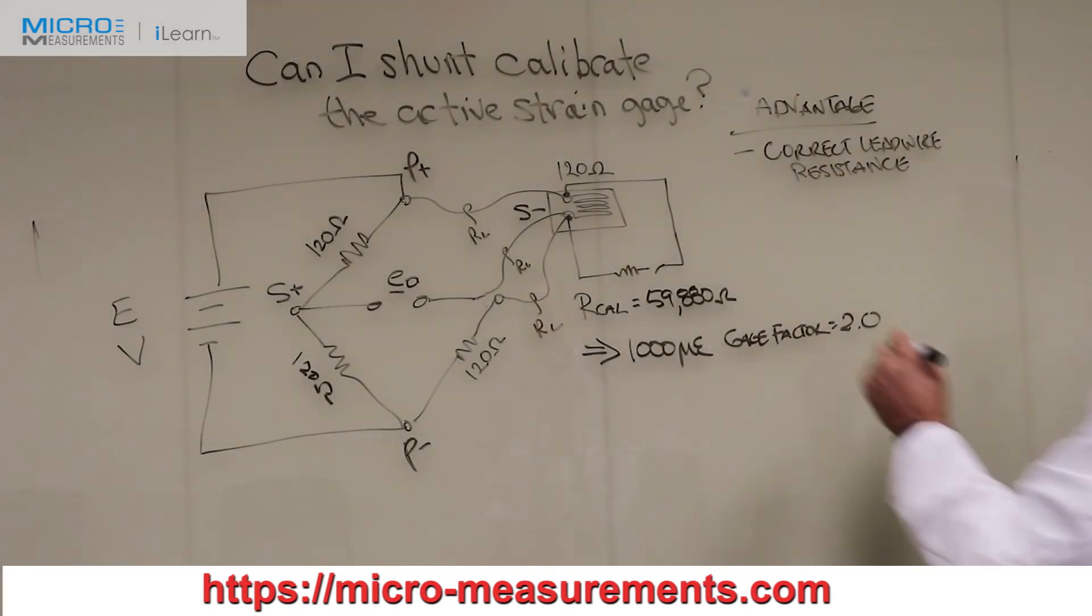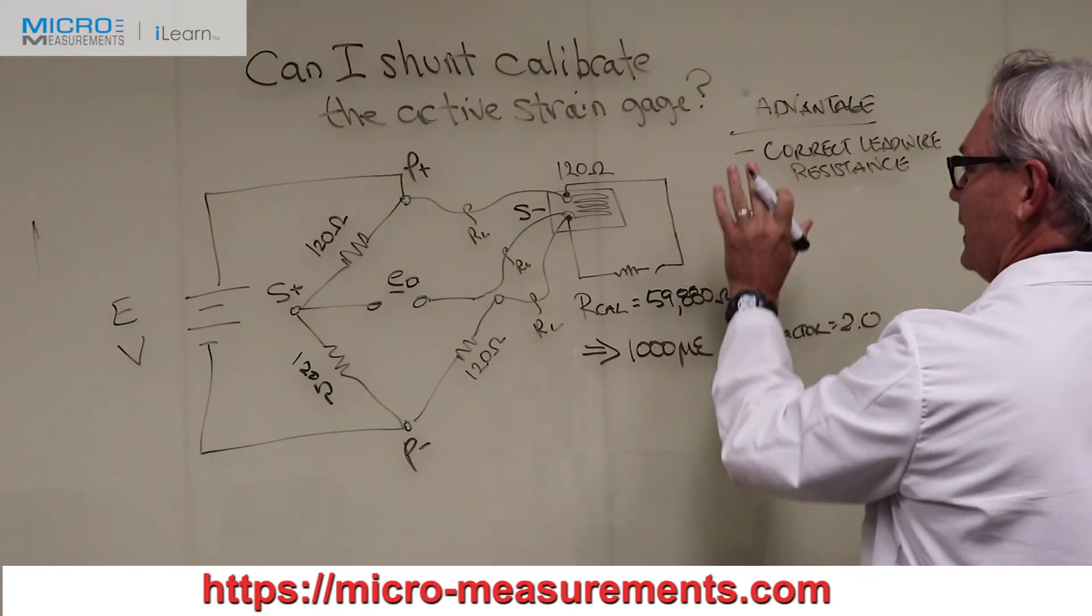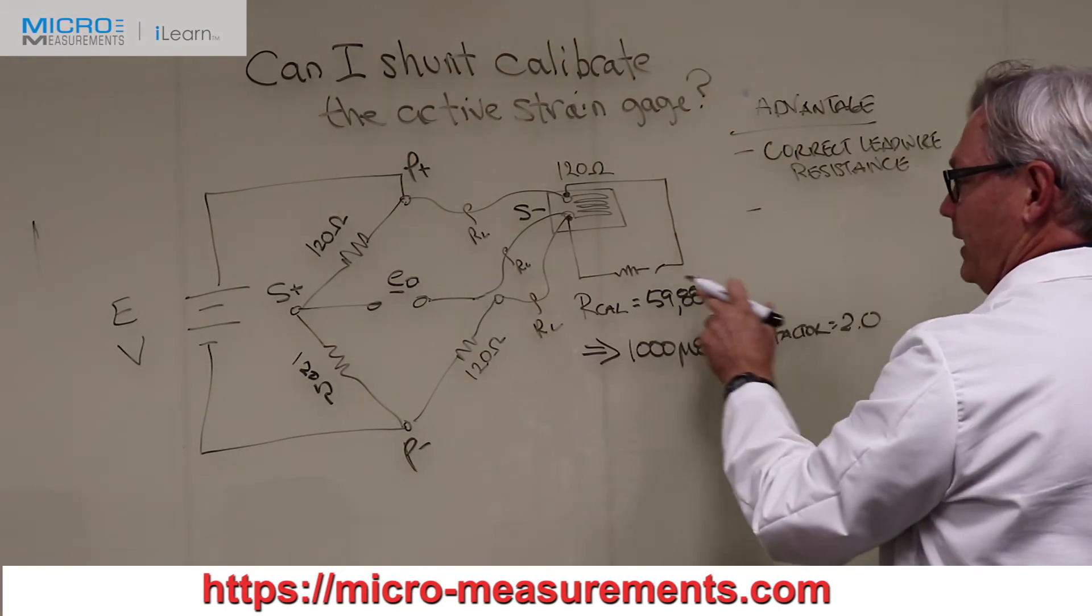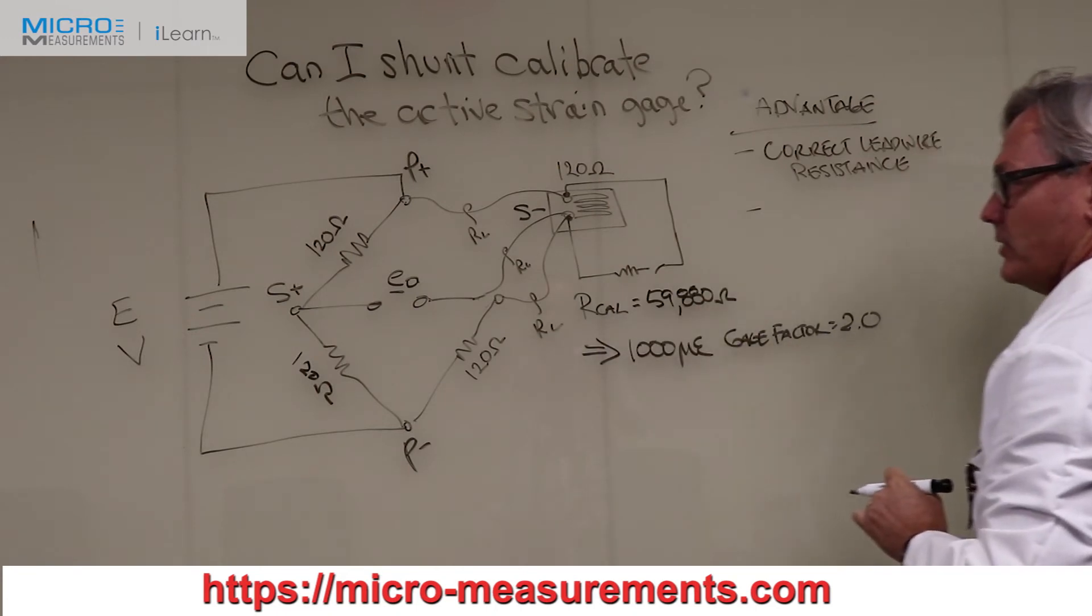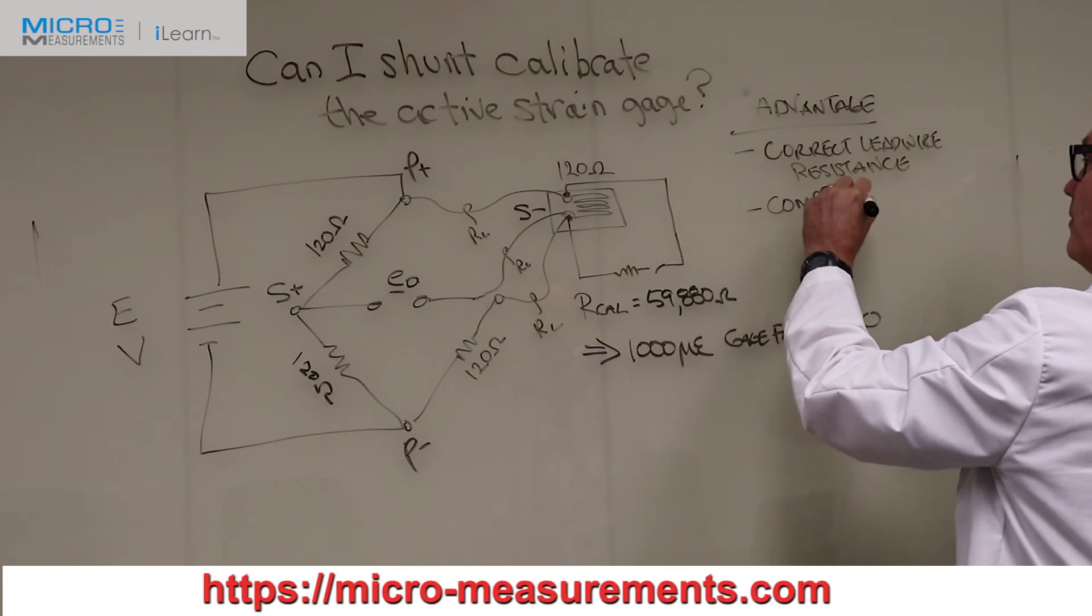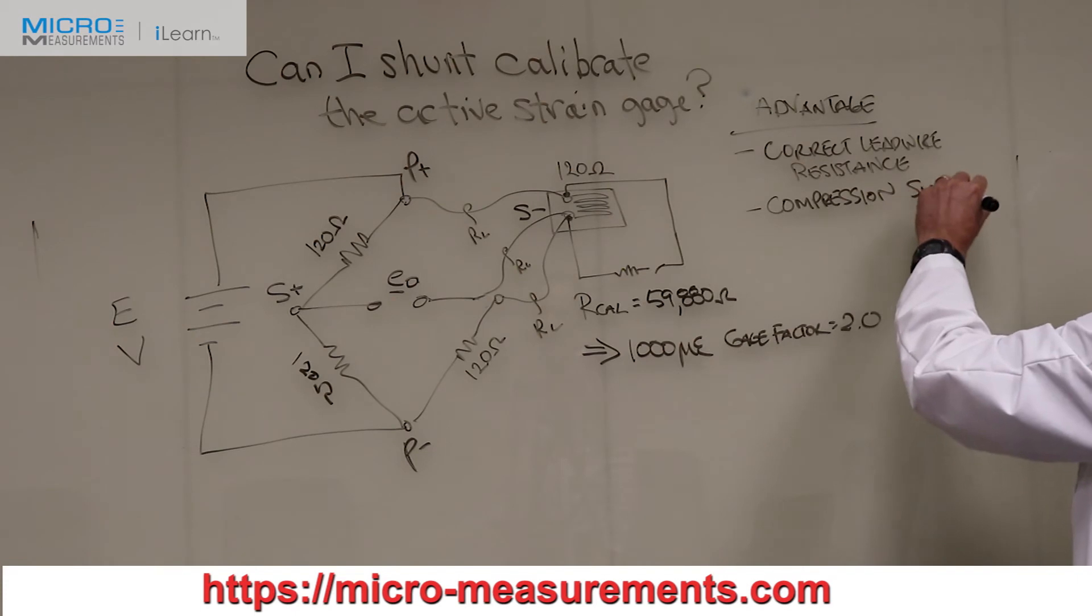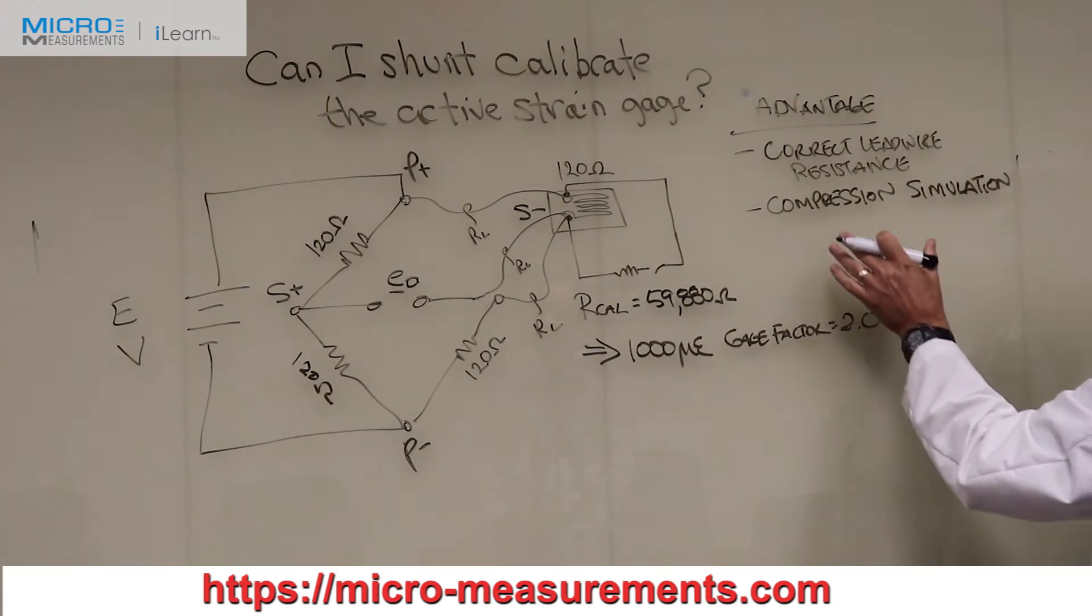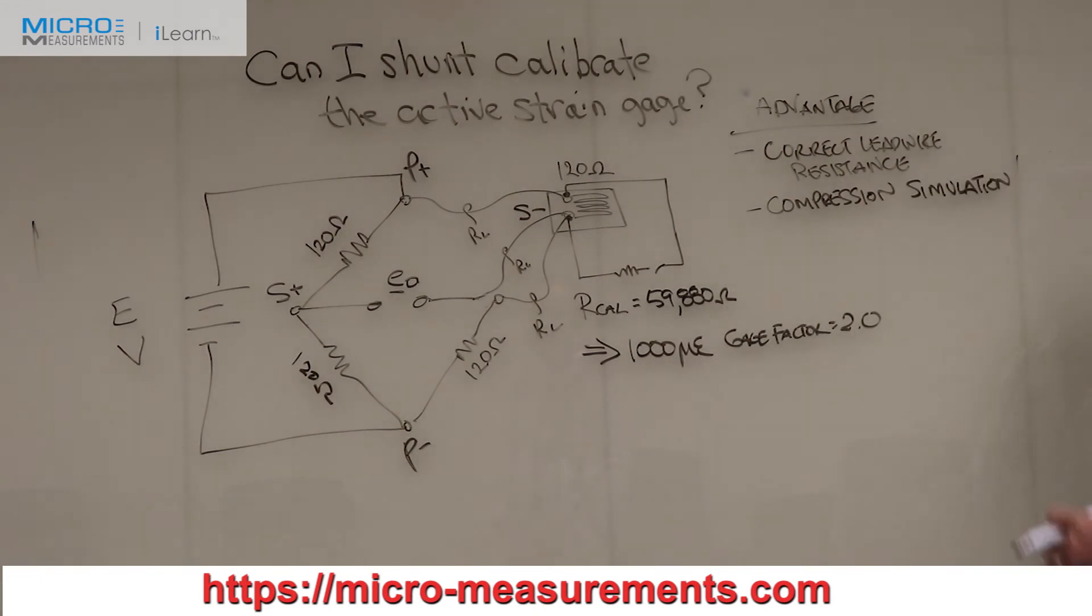Another advantage, and I'm not sure if you'd consider it an advantage or disadvantage, but I'll call it an advantage. Another advantage is that when you shunt this resistor parallel across this active strain gauge, is that it simulates compression. And if you're primarily testing in compression, then I would argue that that's a good thing. You've just simulated a compressive strain just like the strain gauge would see as it were active.